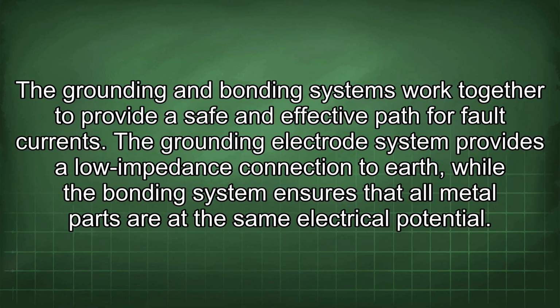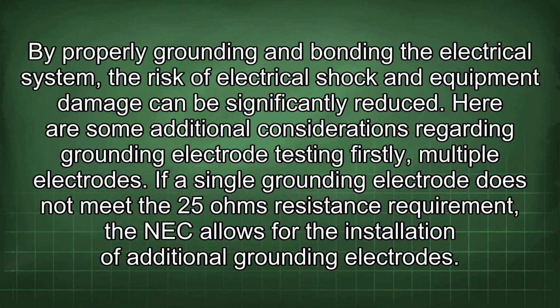The grounding and bonding systems work together to provide a safe and effective path for fault currents. The grounding electrode system provides a low impedance connection to earth, while the bonding system ensures that all metal parts are at the same electrical potential. By properly grounding and bonding the electrical system, the risk of electrical shock and equipment damage can be significantly reduced.